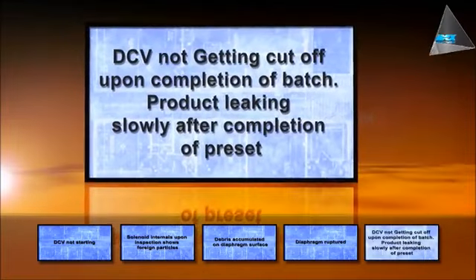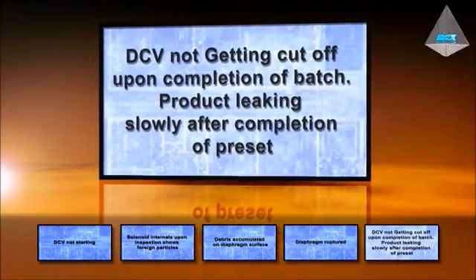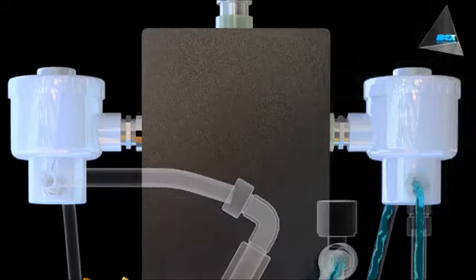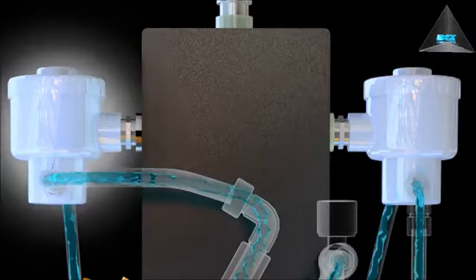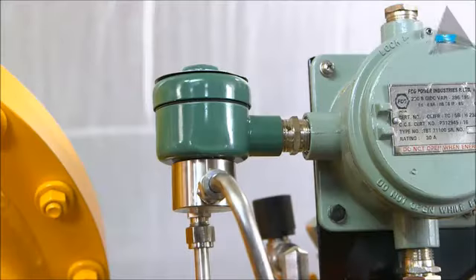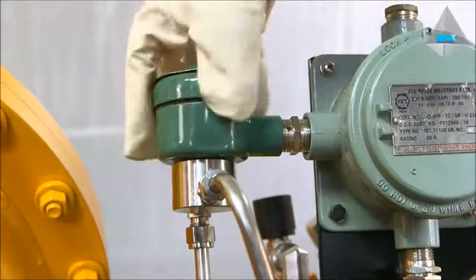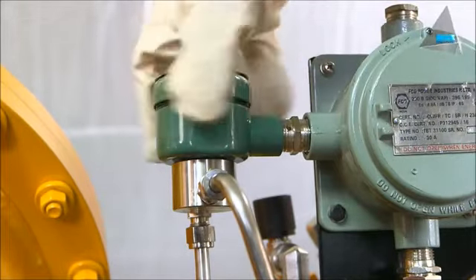DCV not getting cut off upon completion of the batch. Product leaking slowly after completion of preset. Possible cause: valve solenoids not responding. Solution: check solenoid functionality. Replace the coil and solenoid if functionality is not appropriate.